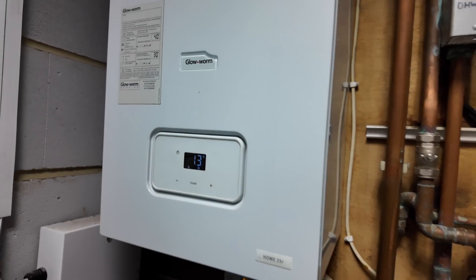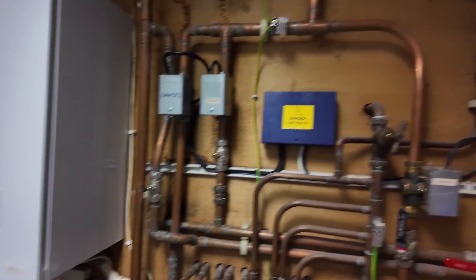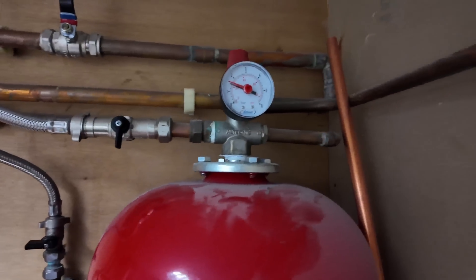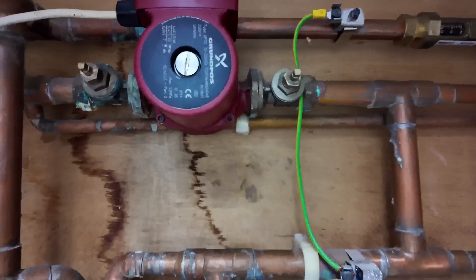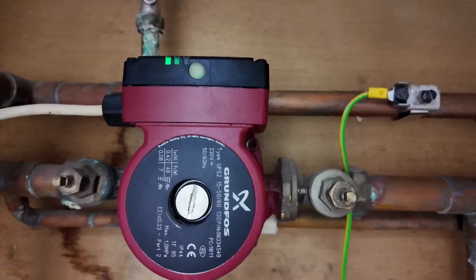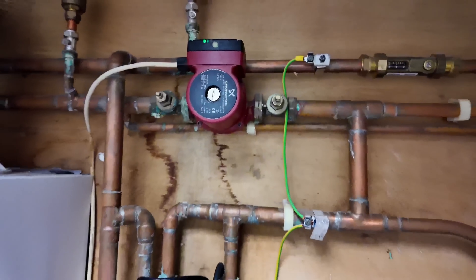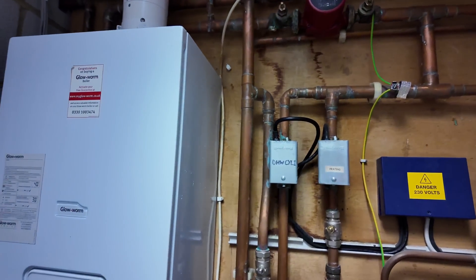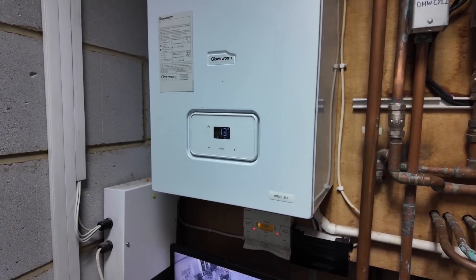Next one: I've got this Glowworm Heat Only Boiler which keeps coming up with an F83 fault. When I came in here first, the pressure was zero, so I've turned the pressure up. But that doesn't sound like it's spinning — it's kind of humming, but stopping and starting. So I reckon that pump might be seized up, which is why we're not getting the circulation, and that's why it keeps coming up with the F83 fault.